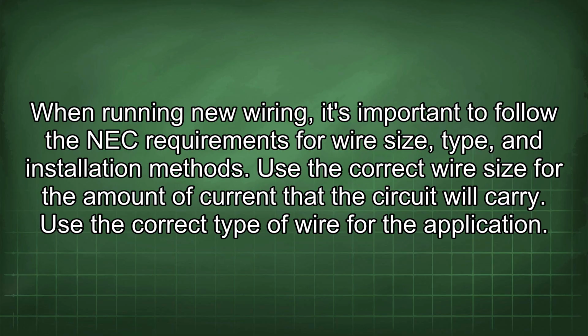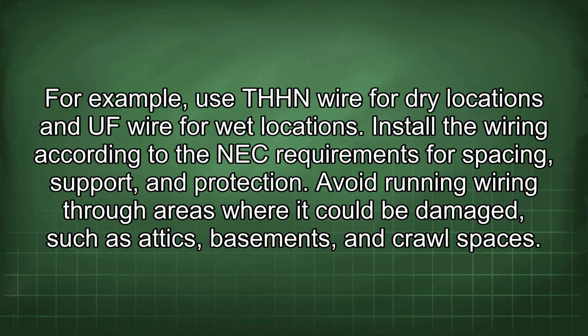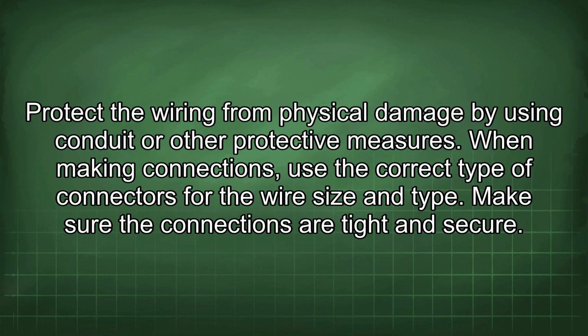When running new wiring, it's important to follow the NEC requirements for wire size, type, and installation methods. Use the correct wire size for the amount of current that the circuit will carry. Use the correct type of wire for the application. For example, use THHN wire for dry locations and UF wire for wet locations. Install the wiring according to the NEC requirements for spacing, support, and protection. Avoid running wiring through areas where it could be damaged, such as attics, basements, and crawl spaces. Protect the wiring from physical damage by using conduit or other protective measures.